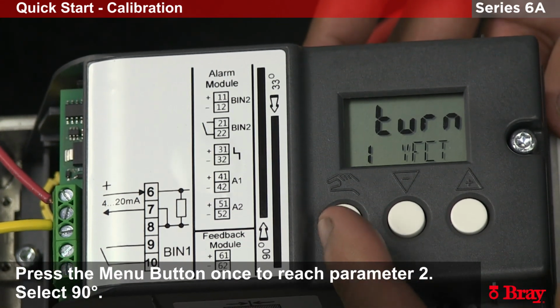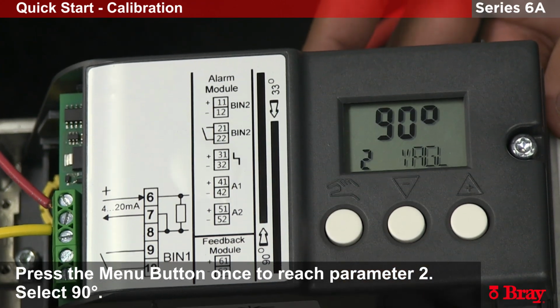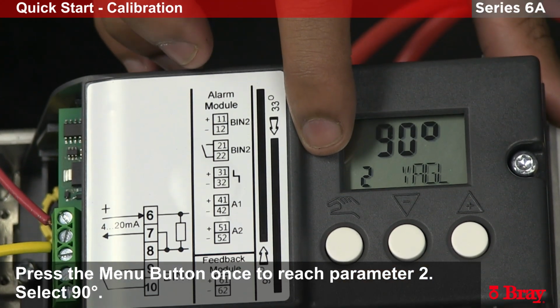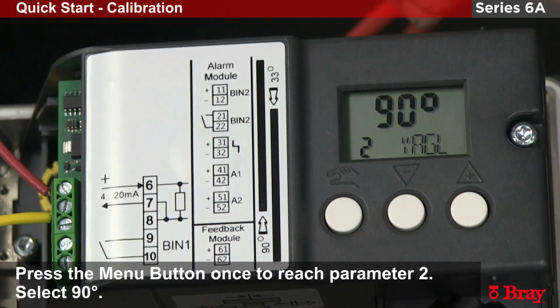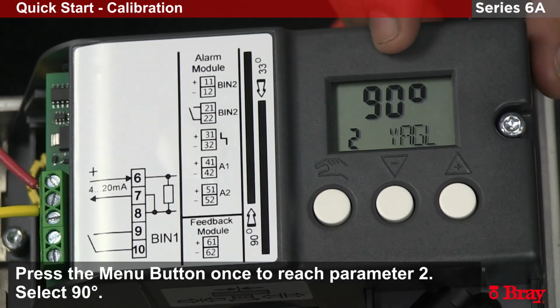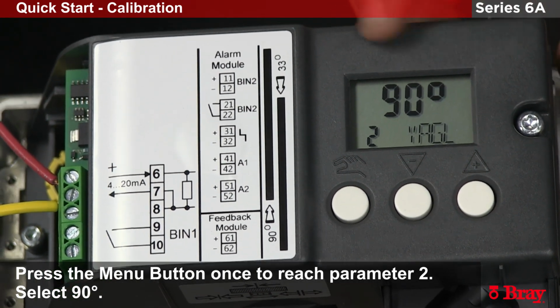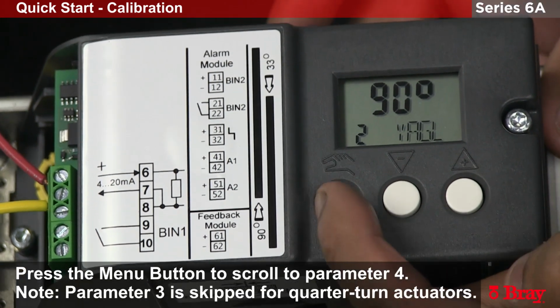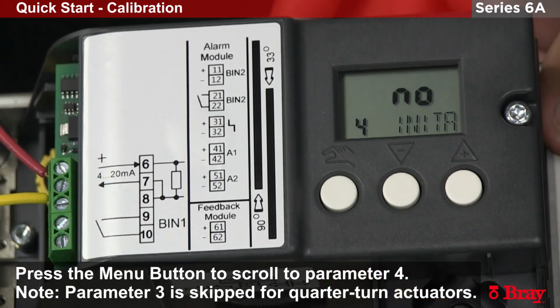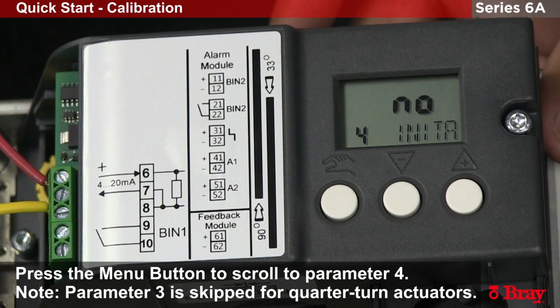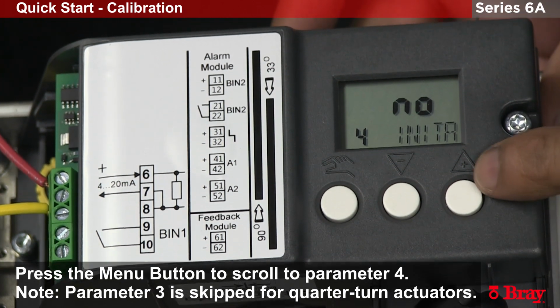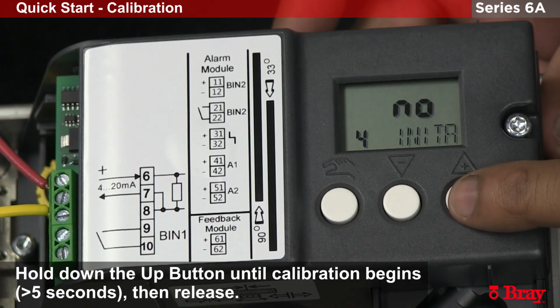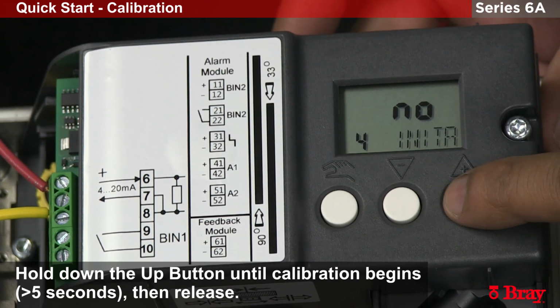We'll hit the hand button once to go to the next window, as indicated in the bottom left corner. We're in window 2. And this is where you state the degrees of travel. As default, it's going to be 90 degrees since we said turn, and we'll leave that as is. We'll hit the hand button again to go to the next window, and this is where we start the initialization. We'll hold down the plus button to start the calibration. Hold down the plus button until the calibration starts.